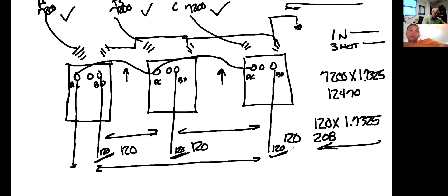Go by individual transformer. What's the voltage here? 120. What's the voltage here? 120. And what's the voltage here? 120. Is any of those giving an indication of a power leg? No, there's no power leg in a Y bank. Only delta has a power or high leg.